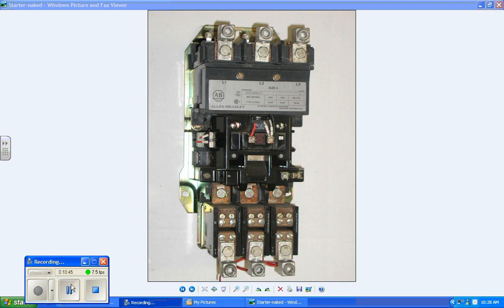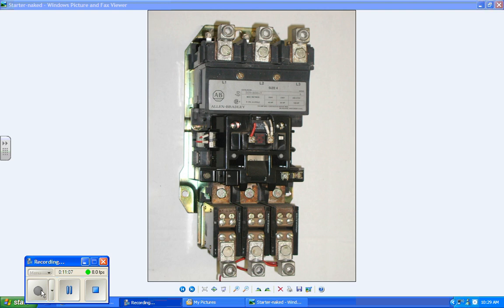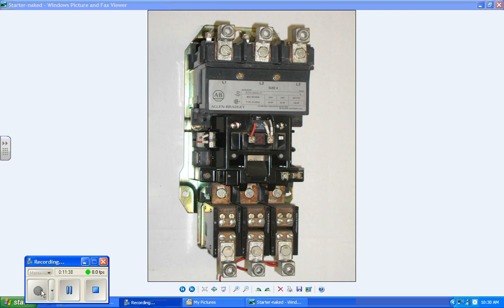Take a look at page 42 of the textbook, Figure 4-15. It shows you a ladder diagram of a three phase motor and the control circuit, and it's indicating three overload contacts. Some of the old motor starters actually had three overload contacts, but when a series circuit is broken in any place, one open all open, right? So there are old ones that you will run into once in a while that physically have three different contacts. So you have to kind of watch for the way it's wired and realize that they've all got to be connected because the three overloads are independent and connected to a single contact.